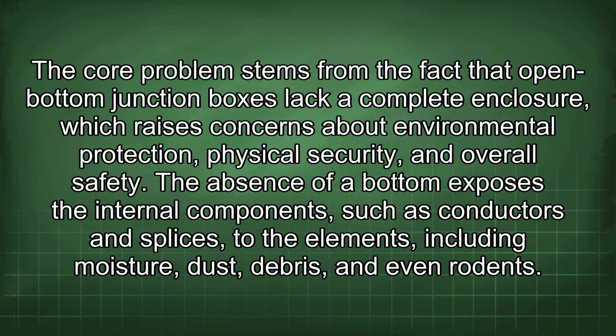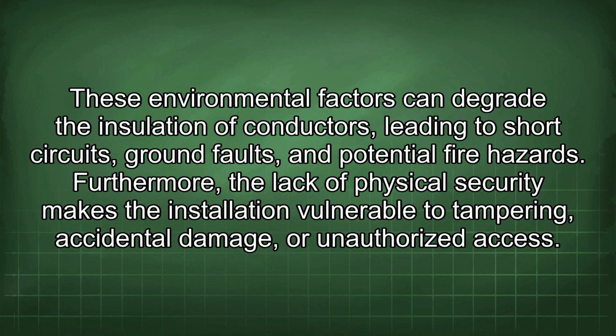The core problem stems from the fact that open bottom junction boxes lack a complete enclosure, which raises concerns about environmental protection, physical security, and overall safety. The absence of a bottom exposes the internal components, such as conductors and splices, to the elements, including moisture, dust, debris, and even rodents. These environmental factors can degrade the insulation of conductors, leading to short circuits, ground faults, and potential fire hazards. Furthermore, the lack of physical security makes the installation vulnerable to tampering, accidental damage, or unauthorized access.